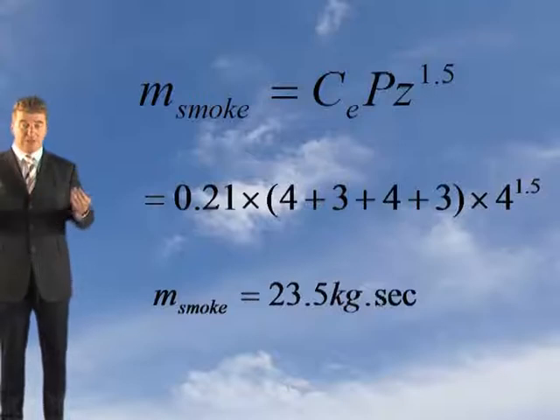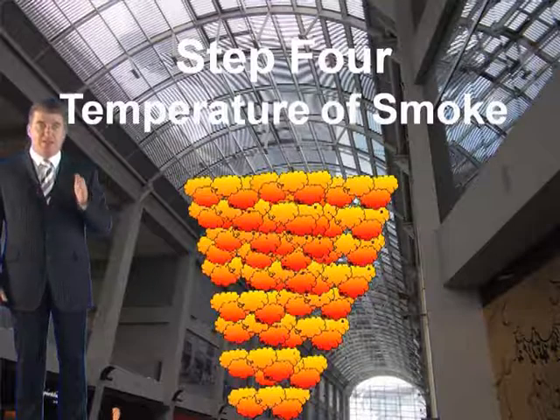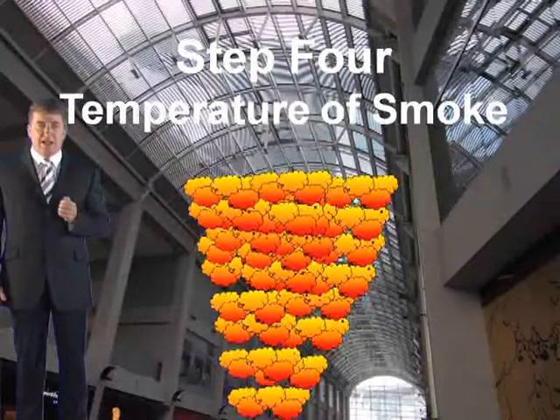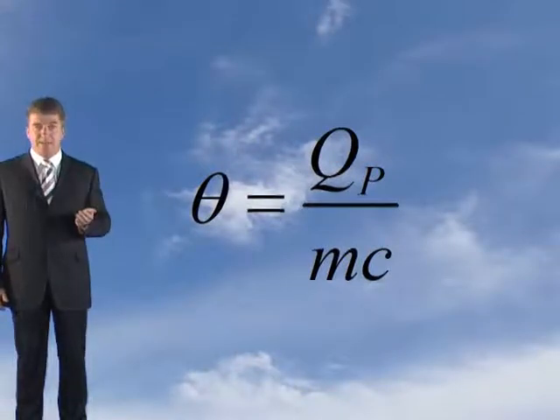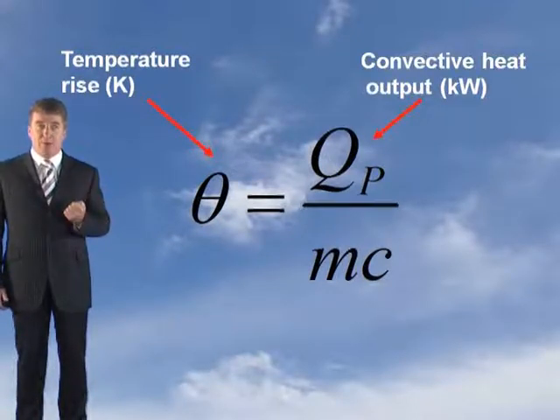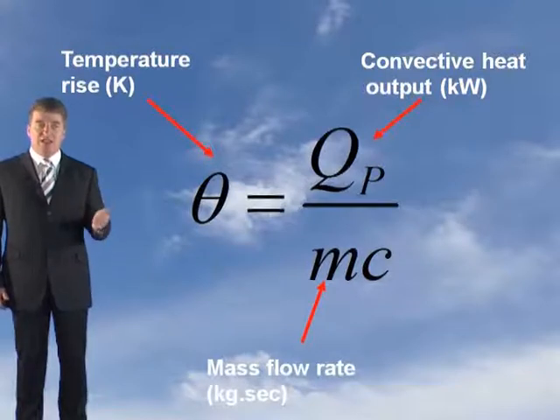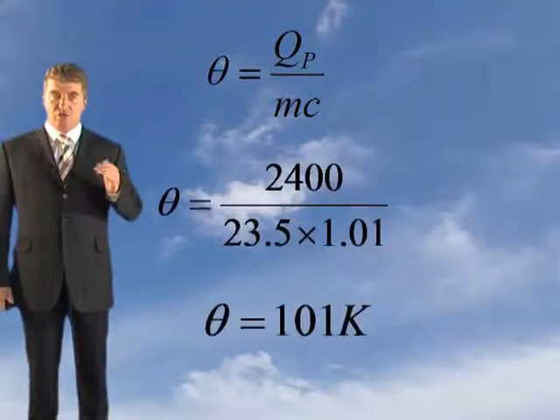So the mass flow rate of the worst case fire is going to be 23.5 kilograms per second — that's what we've got to extract out of that area in each reservoir. Now we know how much smoke has been produced, we need to know how hot it's going to be. Step four is determining the temperature of the smoke. To determine the temperature, you use: theta equals QP divided by mc, where theta is the increase in temperature, QP is your convective heat output, M is your mass flow rate, and C is your specific heat capacity of smoke. Evaluating this gives a temperature rise of 101K.